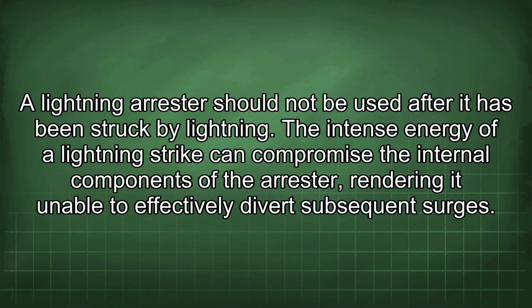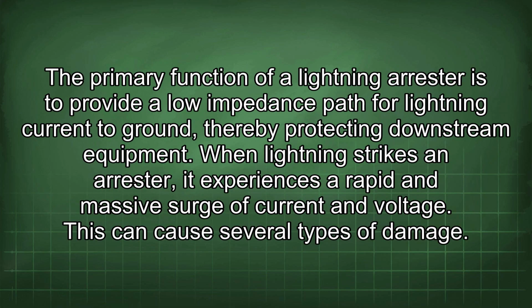A lightning arrestor should not be used after it has been struck by lightning. The intense energy of a lightning strike can compromise the internal components of the arrestor, rendering it unable to effectively divert subsequent surges. The primary function of a lightning arrestor is to provide a low impedance path for lightning current to ground, thereby protecting downstream equipment.